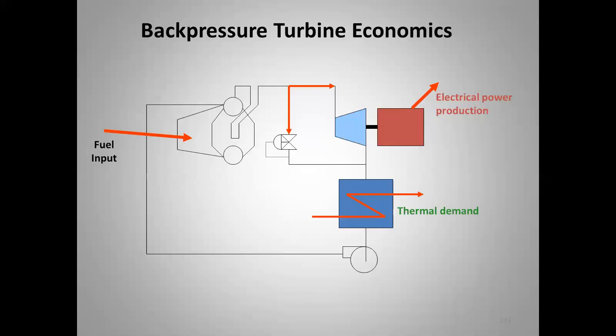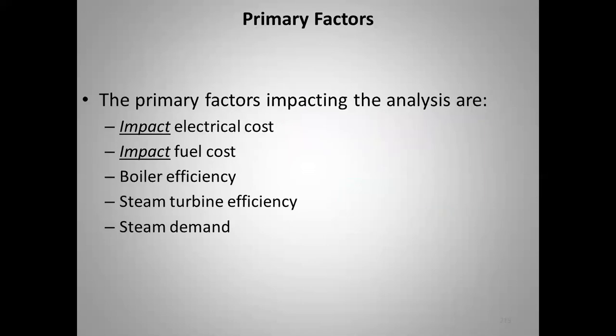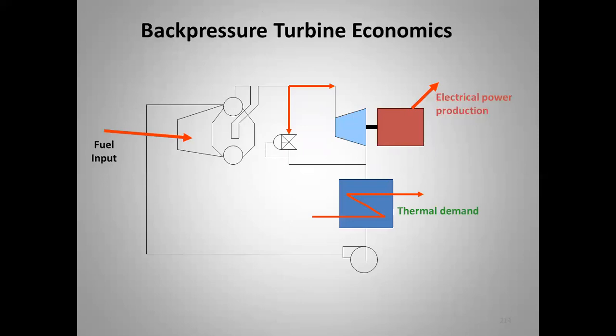Back pressure turbine economics: two paths exist. Going through the PRV means no electricity generation — you satisfy the thermal demand but must purchase all electricity from the utility. Going through the backpressure turbine generates electricity. You need slightly more steam since energy is extracted for power generation, but you can still use most of the turbine exhaust energy for the thermal demand — that's where the economics become really good.